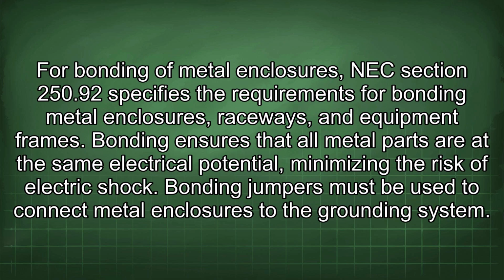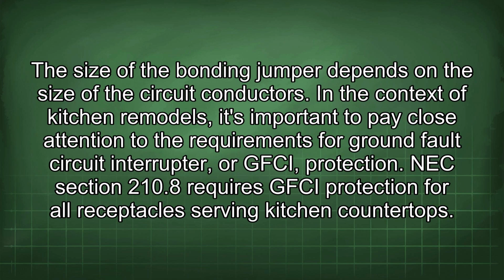For bonding of metal enclosures, NEC section 250.92 specifies the requirements for bonding metal enclosures, raceways, and equipment frames. Bonding ensures that all metal parts are at the same electrical potential, minimizing the risk of electric shock. Bonding jumpers must be used to connect metal enclosures to the grounding system. The size of the bonding jumper depends on the size of the circuit conductors.